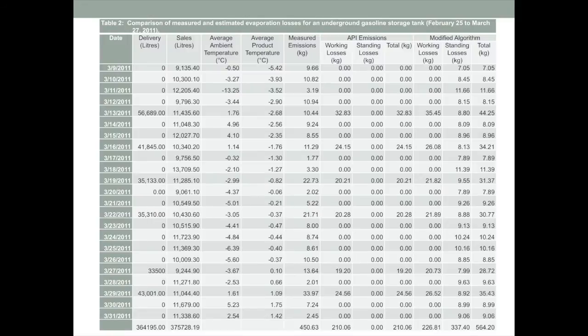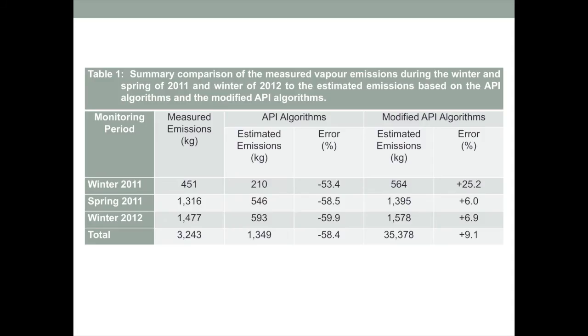We compared our model results to what we measured and what the API algorithms would predict. Rather than show the day-by-day table, I'll skip to what we saw as a function of season. In the first year, the system didn't get running until the beginning of March, so we had about 28 days of data in March. The API algorithms estimated 210 kilograms of product evaporated from the tank for that period, while our measurements showed 451 kilograms of product being emitted — so the API number was low by roughly a factor of two.